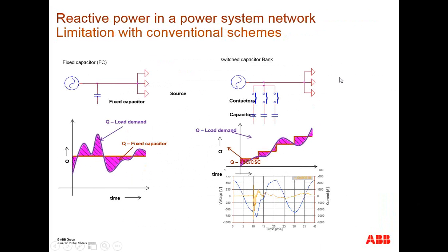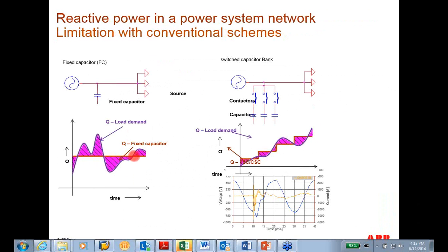If you see fixed compensation, then it will always provide a constant reactive power. But if you look at the nature of the load, it keeps changing from time to time. So it cannot provide the required compensation which is demanded by the distribution network. Then if you look at the switched capacitor, that also minimizes, but it produces a lot of transients. Every time I switch on one capacitor, it produces a lot of transients. It takes 100 to 200 times its rated current. So that also causes disturbance in the network, and sometimes it causes electronic component failure. So even these cannot make a smooth compensation.